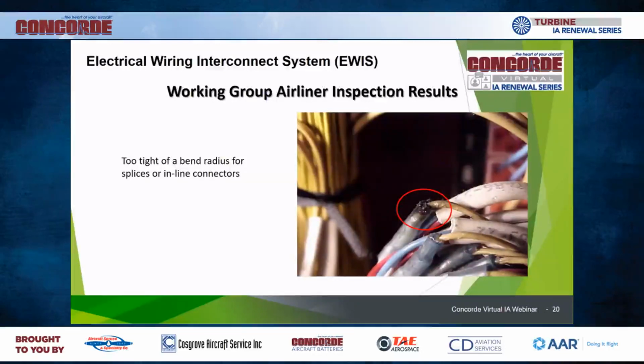In this case, too tight a bend on the radius. It looks like a repair was done, maybe a butt splice, and a butt splice should not be done in a turn at all. It should be done with at least several inches of straight wire on either end. A design office, if asked to give a recommendation on the repair, would not have recommended a repair like this. So if you work for a company with a design office involved, be sure to send them the repair recommendation or repair scheme with all the details of what you're doing, so they can give you the proper design authority and approval for that particular repair.